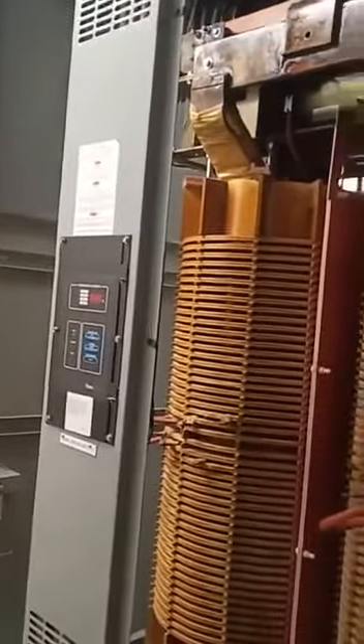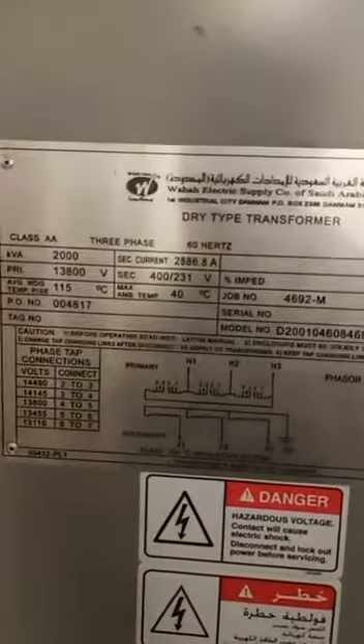Hello friends, in this video I am going to explain how to perform voltage ratio test for medium voltage dry-type transformer. The transformer rating is 2000 kVA and the primary side is 13.8 kV and the secondary is 400 volt.